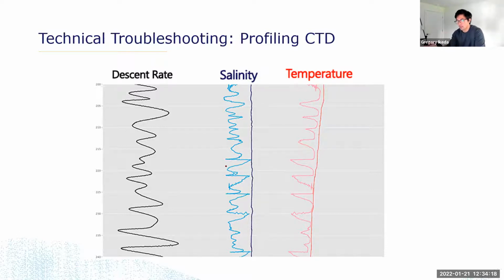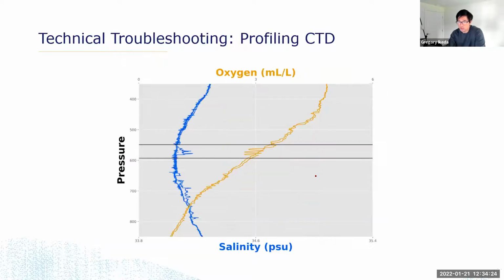So plotting several different parameters can tell you answers you might not get with just salinity or just temperature. Similarly, both conductivity sensors and oxygen sensors are flow dependent, so a pump problem is likely to show up in both parameters. In a separate CTD profile, I noticed fairly erratic data and small spikes in salinity, and suspected another pump failure. By plotting dissolved oxygen alongside salinity, I saw the same kind of signal, confirming it was a pump problem. Again, replacing the cable fixed the issue.